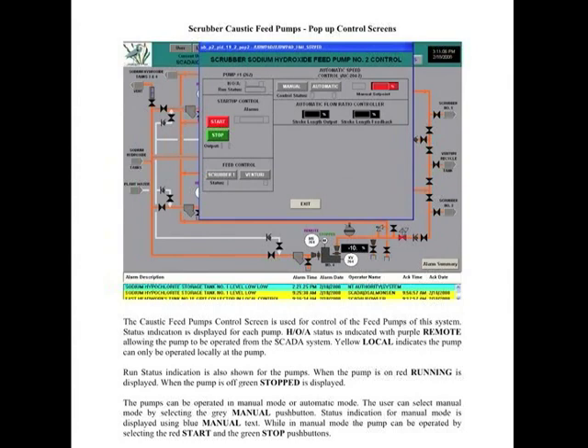In the manual mode, you can just give the pump a set point from 0 to 100, just like most of your other pumps that you have. In manual mode, if you tell it 50%, that is actually going to affect the stroke of the pump. Now, the pump is always going to run at a constant speed, but the stroke will adjust to change the dosage.